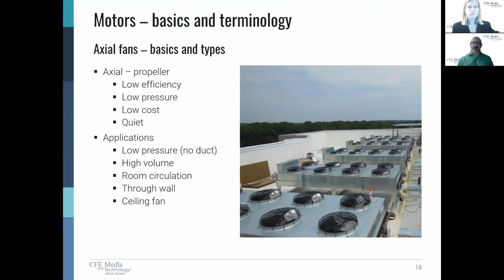So when we talk about fan types, there's two main kinds. We have axial and we have centrifugal. The main design component of an axial fan is that flow is in the same direction as the motor shaft. So basically, it's a propeller style, like the propeller fans you see in a condensing unit. You even have these in your house. These are the fans that you set on the floor that kind of rotate back and forth. They're very cheap. They can't handle any static pressure though.